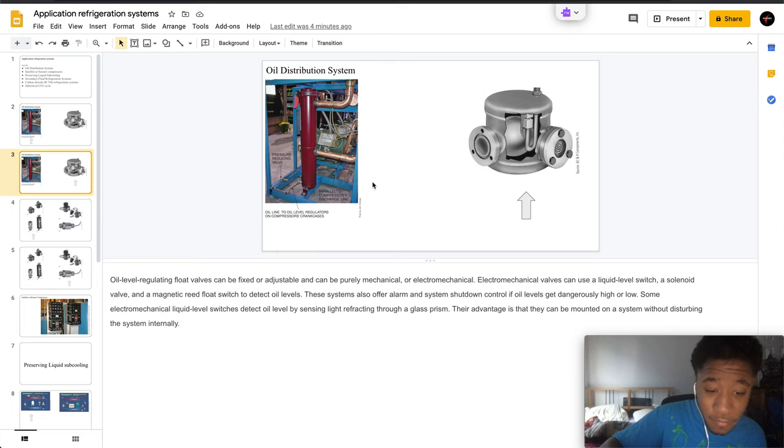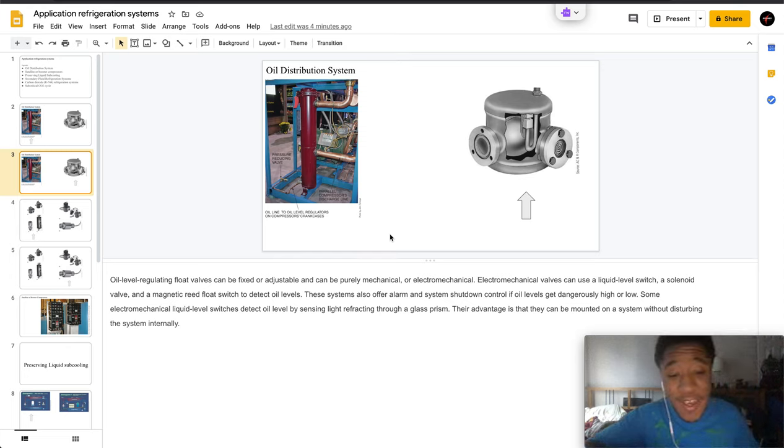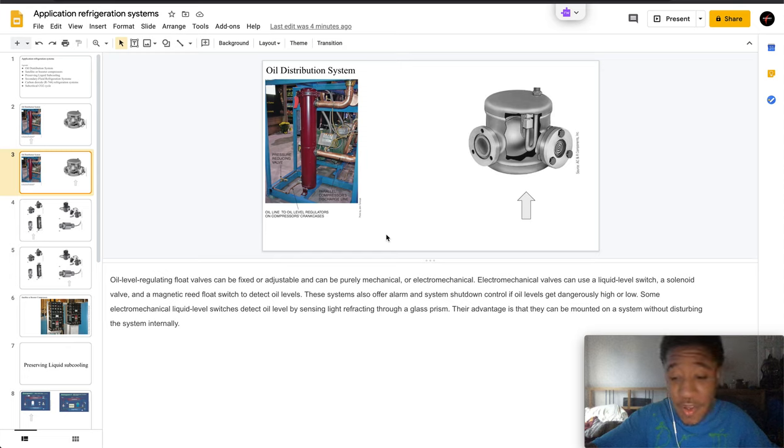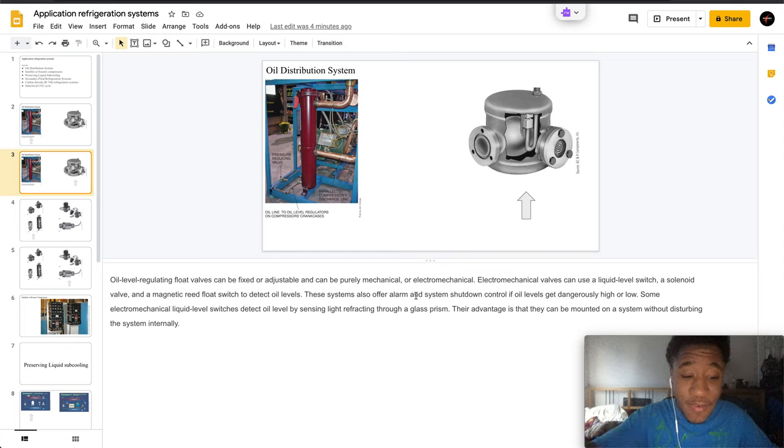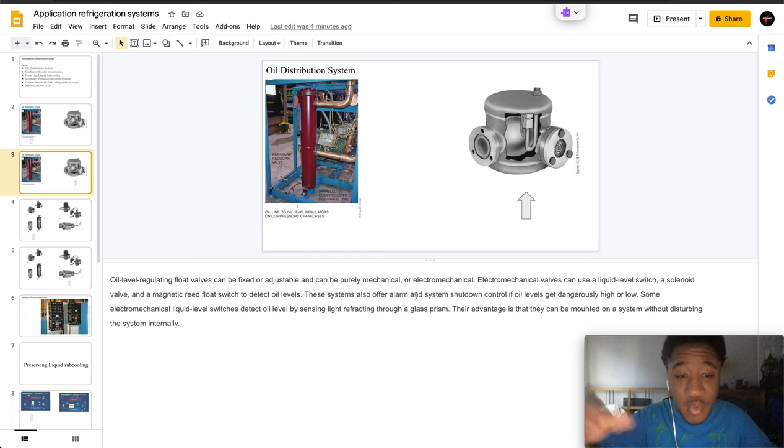The oil level regulator can be fixed or adjusted and is purely mechanical or electromechanical. Electromechanical valves use a liquid level switch and a solenoid valve with a magnetic reed float switch which detects oil levels.